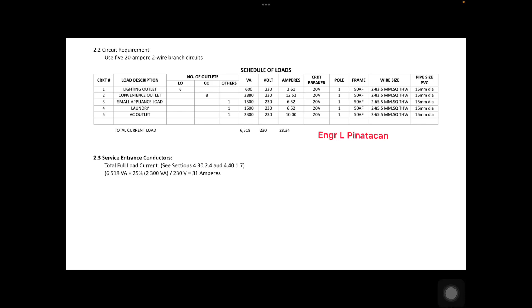Next, we compute the service entrance conductor, which is the total full load current. Per section 4.30.2.4 and 4.40.1.7 of the Philippine Electrical Code 2017, we sum all the apparent power plus 25% of the highest apparent power circuit on the schedule of load, divided by 230 volts, giving 31 amperes. The Philippine Electrical Code recommends 14 mm² TW wires as the service entrance conductor for this system.